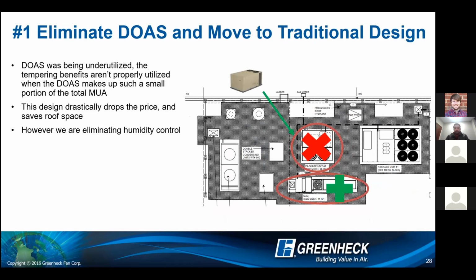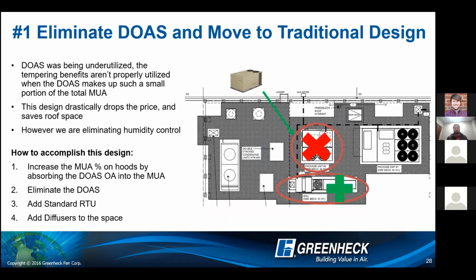So that DOAS, I'm sure you recognized from that first slide, was being heavily underutilized. The tempering benefits aren't there when you're utilizing such a small proportion of the total makeup air. So this design is going to be drastically cheaper, and it's going to save on overall roof floor plan space. However, the big loss here is we are eliminating humidity control. We're going to increase the makeup air percent on the hood to absorb the outside air from the DOAS unit. So most of this makeup air is going to be traditional, heated and cooled, but we're totally eliminating humidity control. So that kitchen has the potential to be very uncomfortable. However, it is a much lower price point.